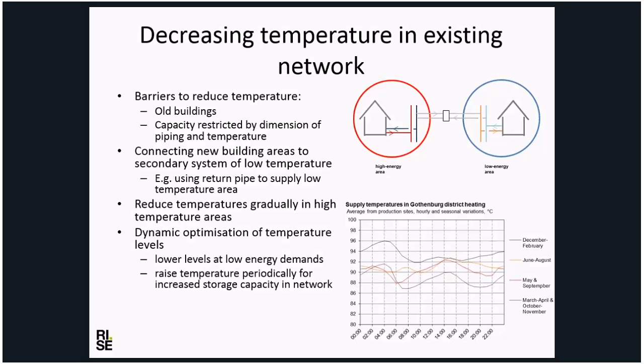The diagram here is an example from Gothenburg. The 4 different curves you see there represent different seasons of the year. If you look at the upper curve, the blue one, it represents winter, and this shows the variation of temperature during an average day. So here you can see that the temperature is increased by a couple of degrees in the early morning in anticipation of peaks in the morning, which means that you may not need to start the peak boilers, or you can have a lower load in the morning.